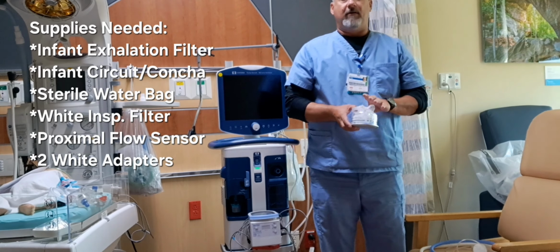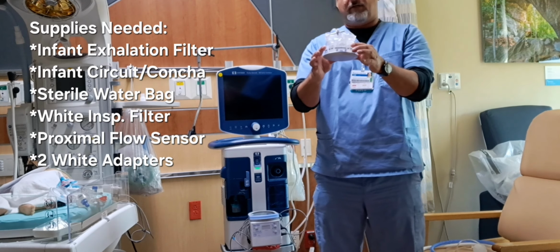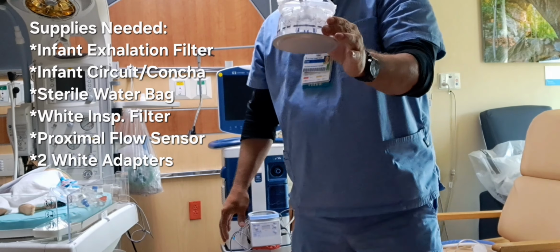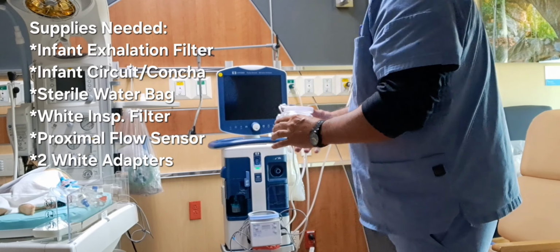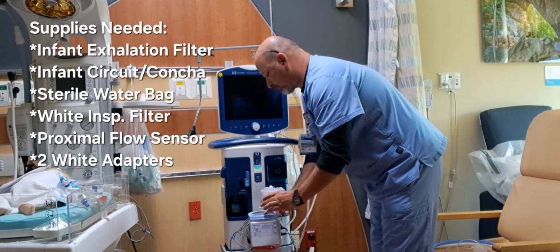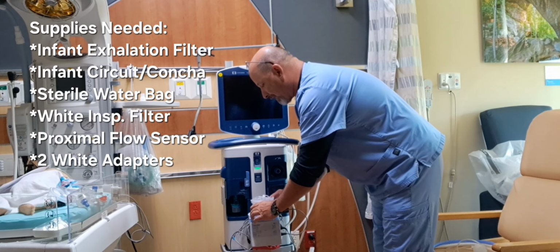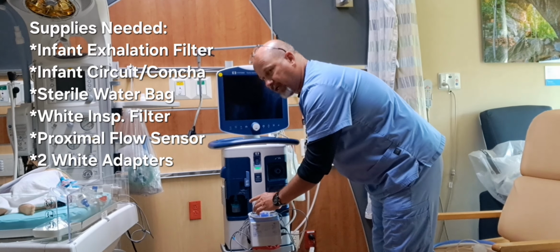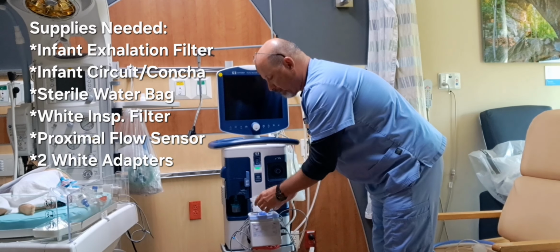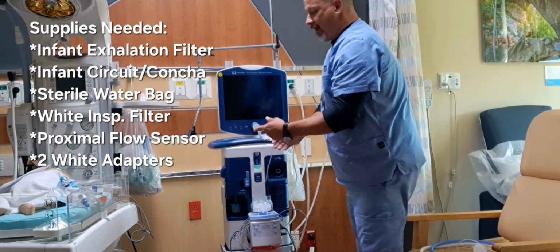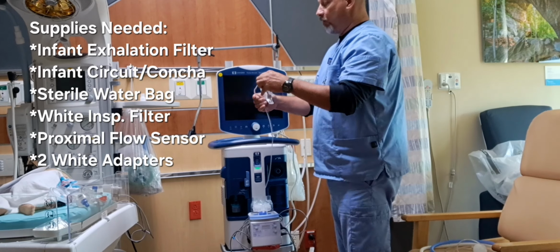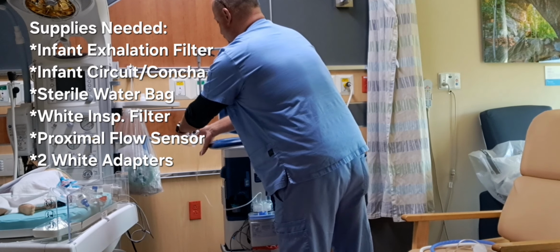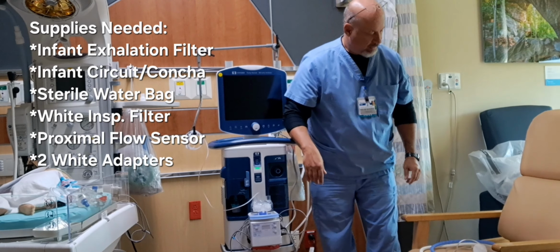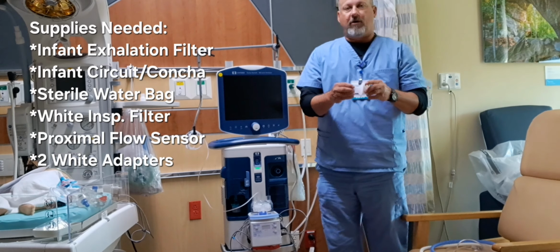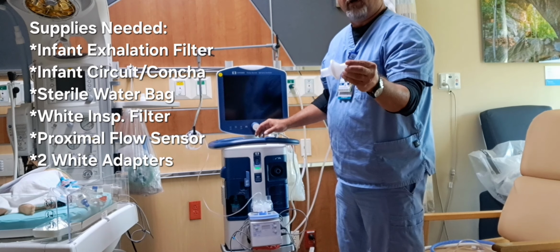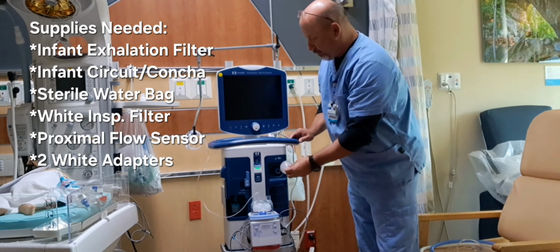Next thing I'm going to hook up is my concha, and this comes in the packaging with the circuit. It goes on the top of your heater. Just press the blue lever down, slide that over until it locks in place. You'll hear it clicking. I'm going to unravel my water line pretty much just to get it out of the way. Put it right there. Next thing I'm going to do is put on my white inspiratory filter on the inspiratory side of the ventilator, which is right here.